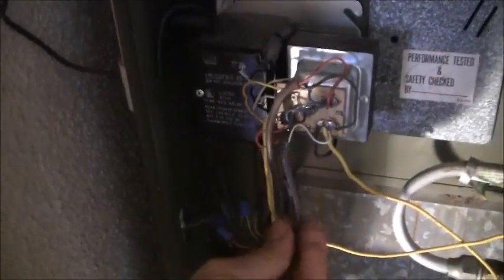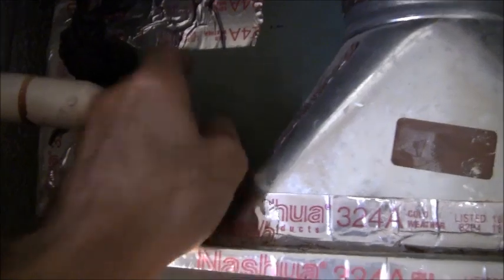It interrupts the line that goes to the compressor, which is, this is the thermostat wire that goes to the compressor contactor. You're going to put that in line with this float switch, taking out the condenser. This way you're not going to operate the condenser unit continuously if your main line is backed up, so you won't flood out with water. It's a safety. They're only $15 and they're well worth it, and they should be installed. This thing is so old it doesn't even have the port to put it in, so it doesn't matter.